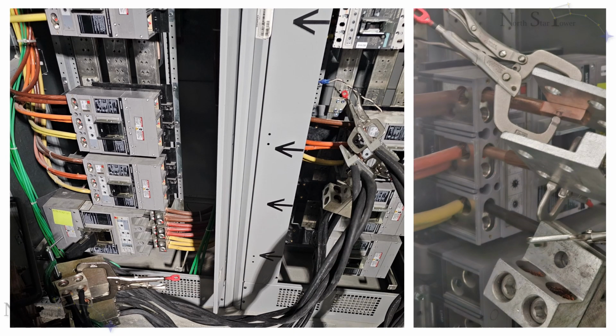Primary injection gives us the most accurate, real-world simulation of these trip conditions. The test set generates a controlled high current at low voltage, safe for technicians and non-destructive to the breaker. We document trip times and compare them to factory specifications, verifying that the trip unit is operating as intended.